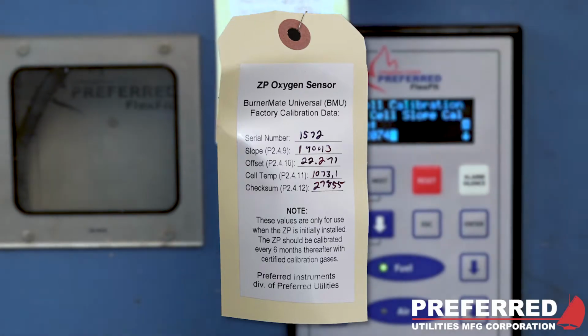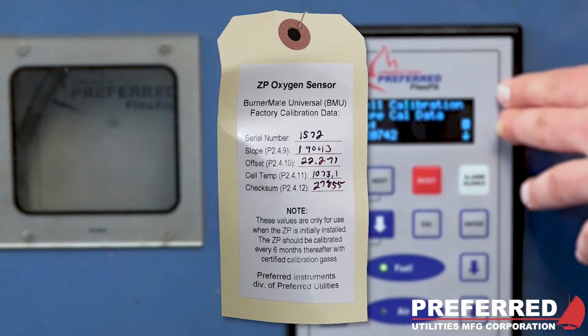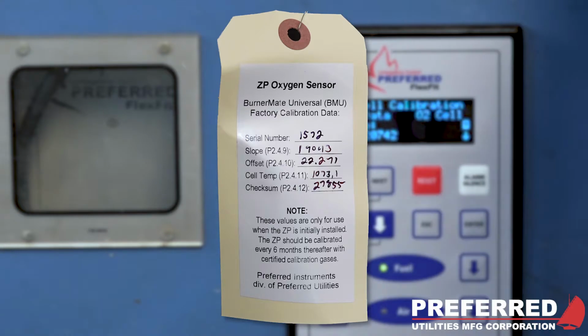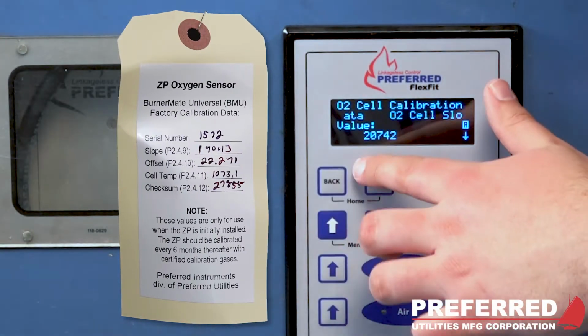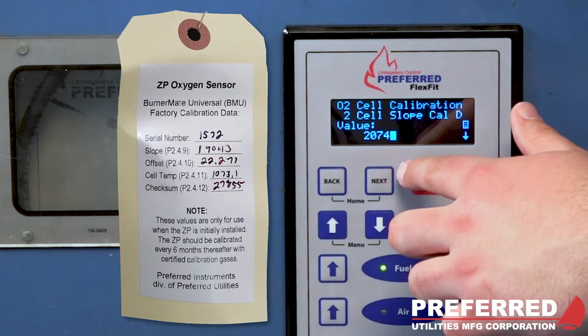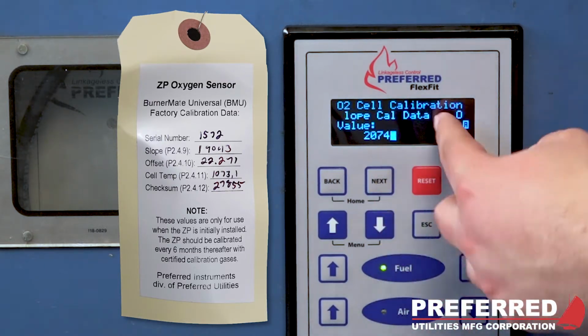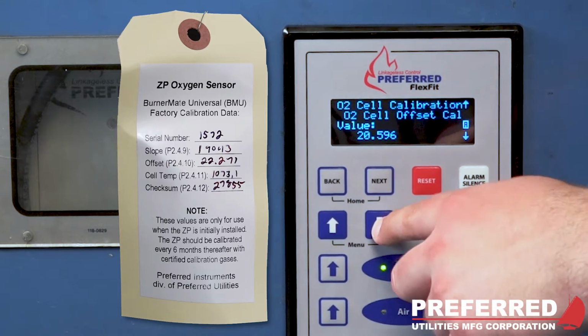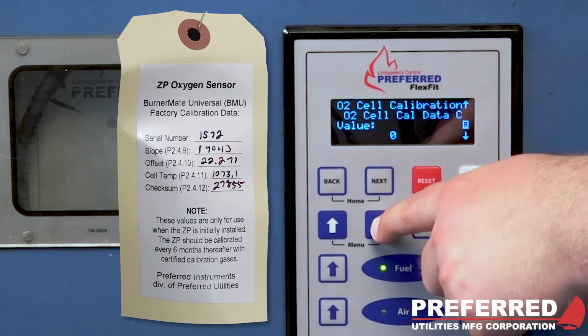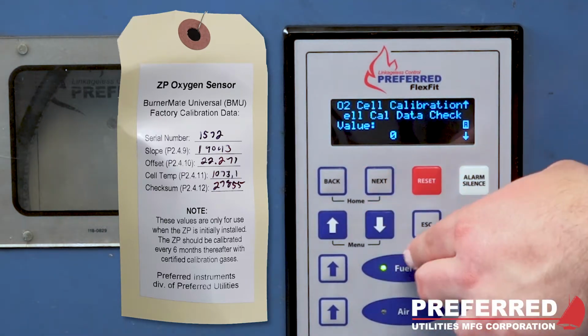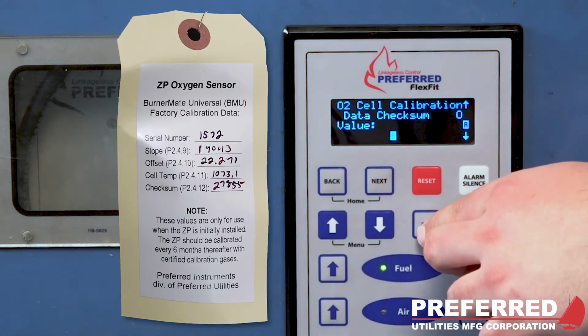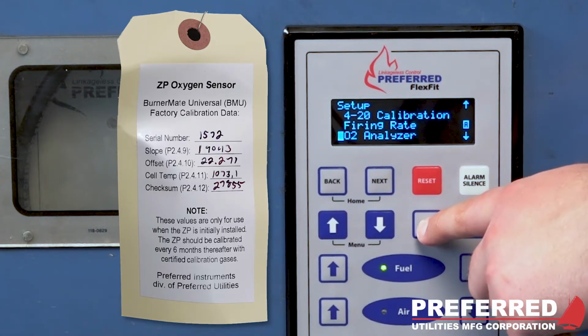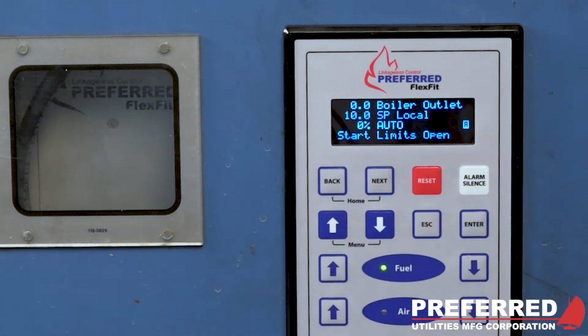And this is the calibration data that needs to be paired up with your controller. So it will give you 5 different numbers, one for serial number, one for slope, one for offset, one for cell temp, and one for checksum. Then you'll go into your O2 cell calibration, and here it's asking for the number for slope, and then offset, and so on. You would just enter that data into your calibration data. Once you're done, you can back out, and that will complete your O2 sensor setup.